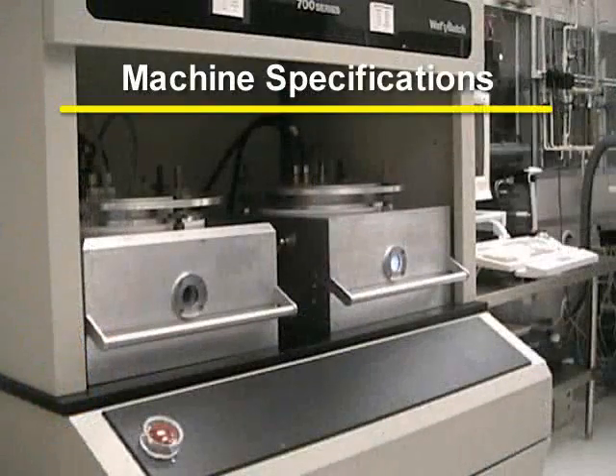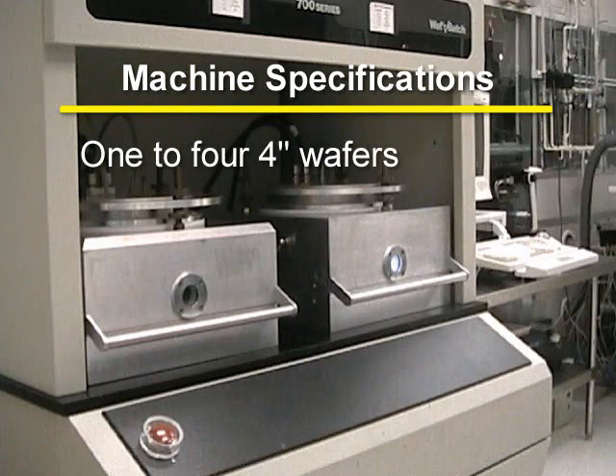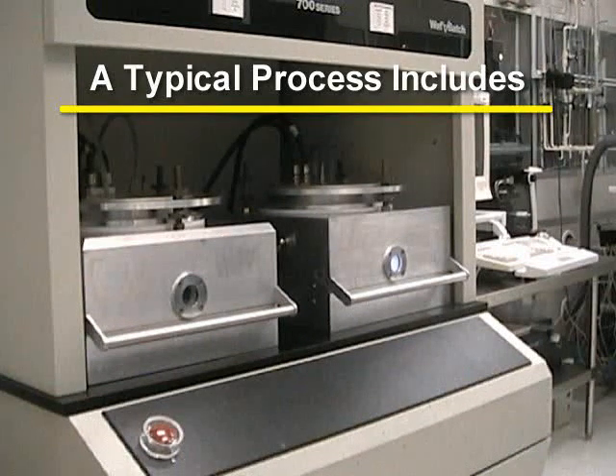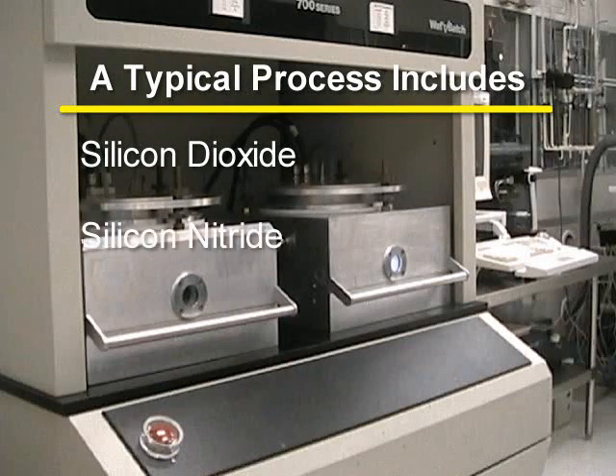The Plasmatherm PECVD can process a wide range of sample sizes. The number of samples depends on the size of the samples. A typical run can process anywhere from 1 to 4 4-inch wafers. Typical deposition rates range from 100 to 400 angstroms per minute. Typical processes include silicon dioxide depositions, silicon nitride depositions, and silicon oxynitride depositions.